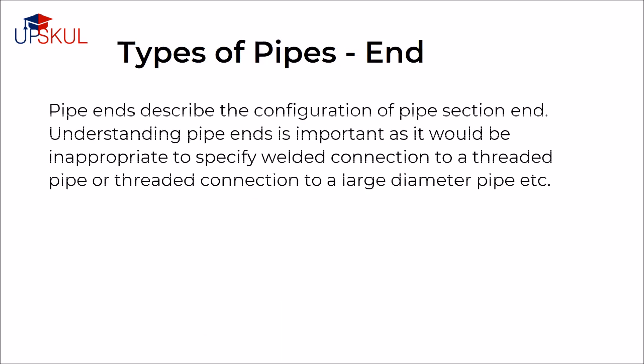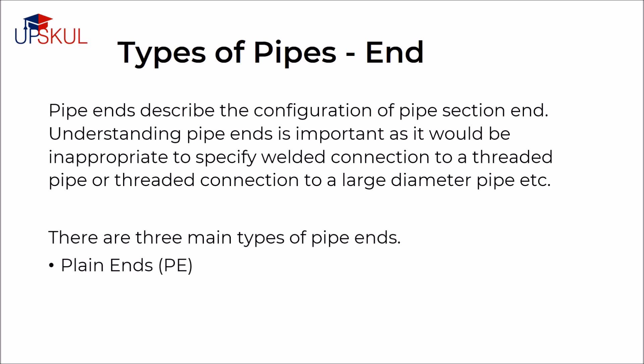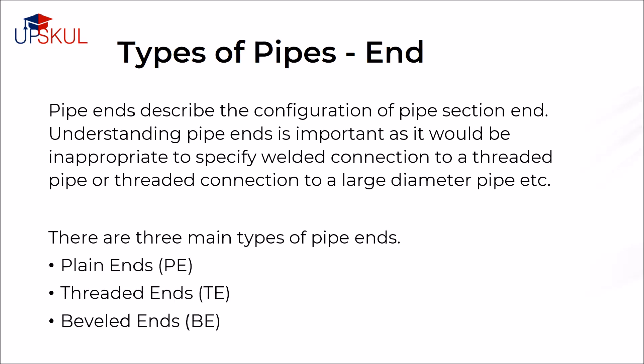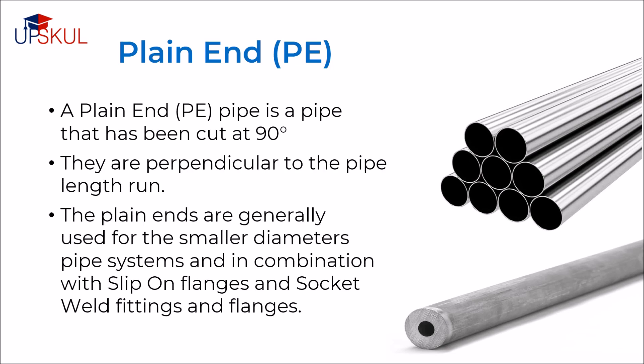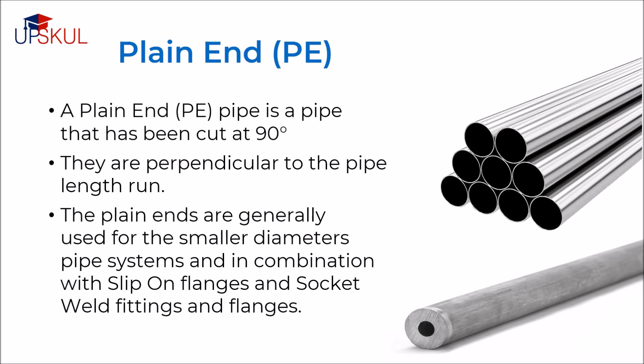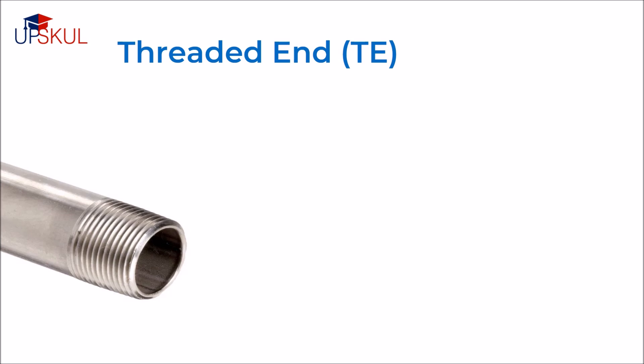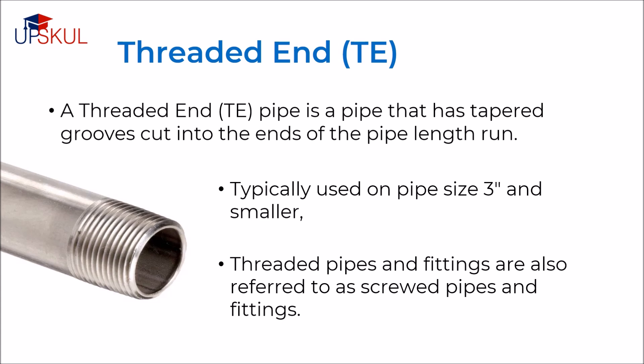The last classification of pipe is based on the pipe ends. Pipe ends describe the configuration of a pipe section end. Understanding pipe ends is important as it would be very inappropriate to specify a welded connection to a threaded pipe or a threaded connection to a large diameter pipe. There are three main types of pipe ends: plain ends, threaded ends, and bevel ends. A plain end is a pipe that has been cut at 90 degrees perpendicular to the pipe length. Plain ends are generally used for smaller diameter pipe systems in combination with slip-on flanges and socket weld fittings and flanges. A threaded end pipe is a pipe that has tapered grooves cut in the ends of the pipe, typically used for pipe sizes that are 3 inches or smaller.